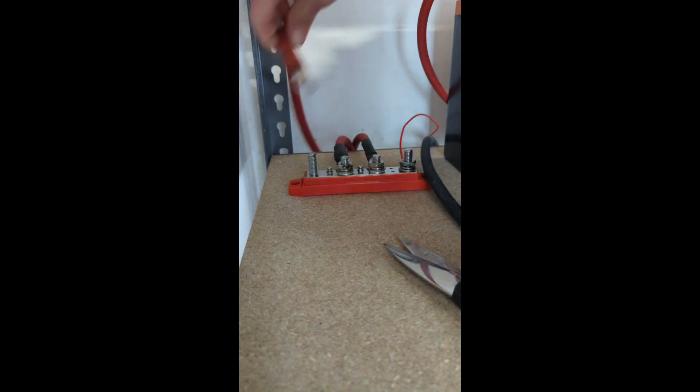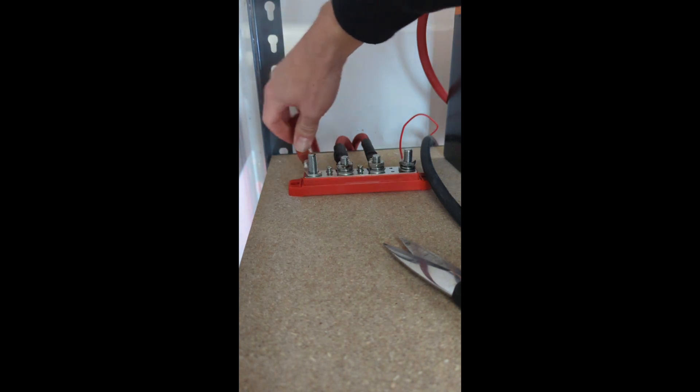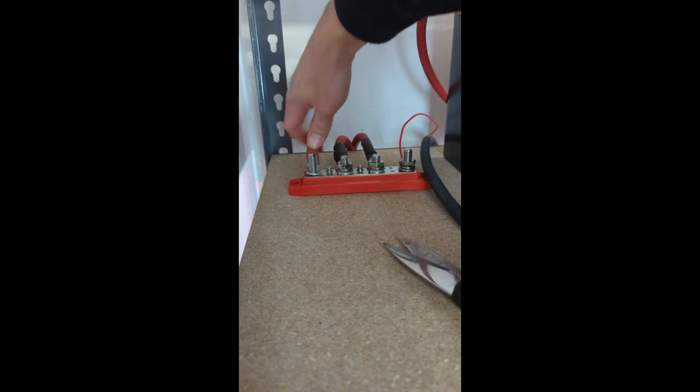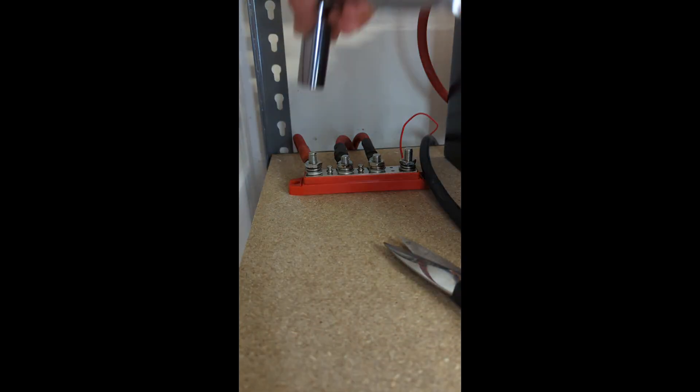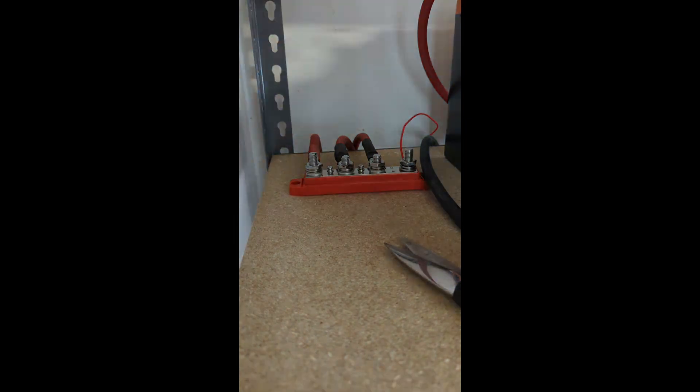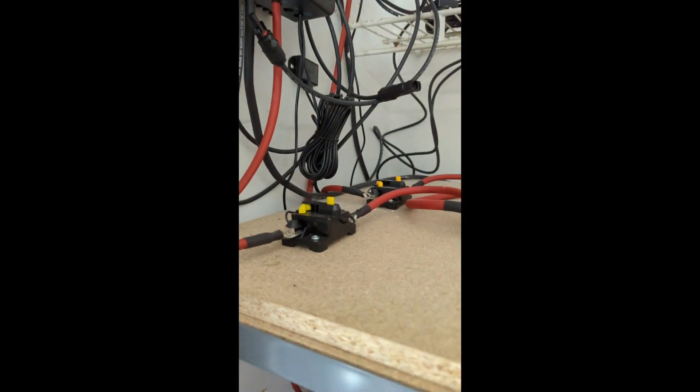We're going to get a little bit of spark on this one. This is going from the main charge controller and inverter. You can avoid that spark if you use a pre-charge resistor. It will spark like that when the capacitors are energizing in the solar charge controller. All of our connections are now tight and we can turn everything back on.